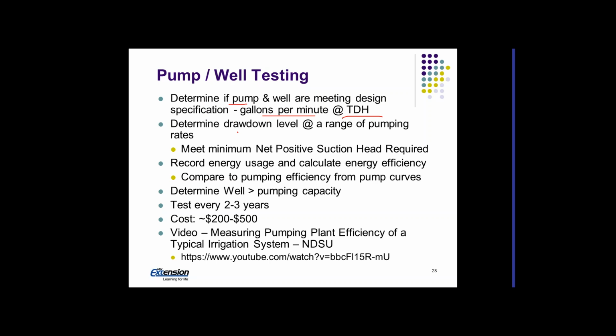We're also going to look at the drawdown level at a range of pumping levels and make sure that the net positive suction head requirement is met. I had a neighbor who had a pump that wasn't low enough, and basically what happens if they're not low enough, they start surging water, or they'll start cavitating. So you're just sucking air basically. So that can be an issue.